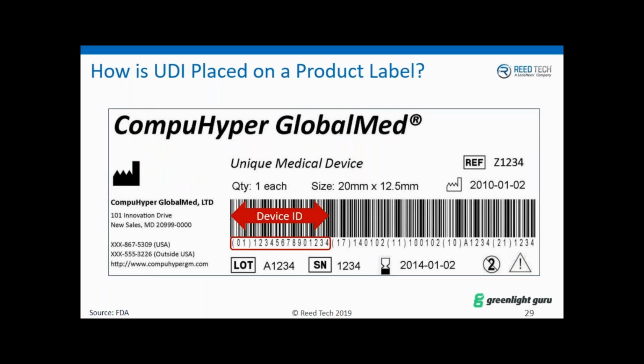a UDI looks like that number underneath the barcode, and the presentation is in a linear barcode. I happen to use a GS1 example here, but the first 14 digits, preceded by parenthesis 01 close parenthesis, the application identifier for a device, are concatenated with a production identifier depending on the presence of those controls on the label itself. So there might be a manufacturing date, expiration date, lot or serial number, that type of controls, and that's very much similar. Rules are a little bit different, but the presentation would be easily understood. And in some cases, if you elect to, you can use the very same GTIN number for your FDA and European Union marketing.